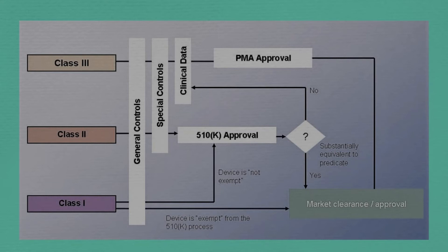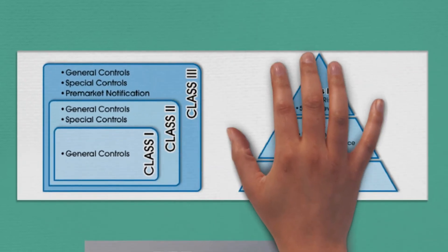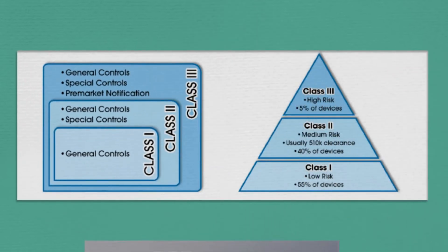Class 1, Class 2, and Class 3 devices all require general controls. Class 2 and Class 3 require general plus special regulatory control, and Class 3 devices require general plus special regulatory controls as well as pre-market approval. FDA has categorized more than 1,700 medical devices into these three categories. Nearly 55% of medical devices fall under Class 1, 40% fall under Class 2, and the remaining 5% fall under Class 3.